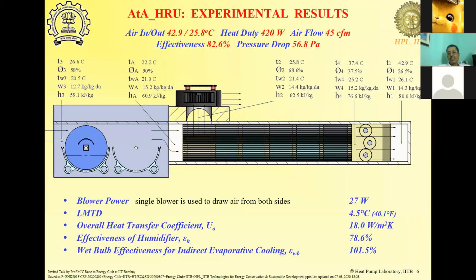So if we can pass this air through a liquid desiccant solution, now a similar system is put up on this side where you replace the water with liquid desiccant. When the air passes over the liquid desiccant contacting media, unlike here where the water evaporated, with the liquid desiccant the water vapor will condense into it, and instead of the temperature dropping, the temperature will increase. The RH, instead of rising here, with liquid desiccant present, which is hygroscopic, will reduce, and then that hot dry air can be put in from this side. And then even in Mumbai, we can operate a system like this, provided we dehumidify the air first. And the dehumidification can be enabled using liquid desiccant.